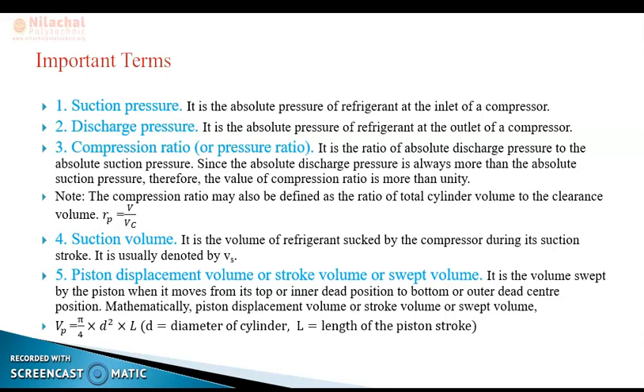The next term is compression ratio, also called pressure ratio. It is the ratio of absolute discharge pressure to absolute suction pressure. Since absolute discharge pressure is always greater than absolute suction pressure, the compression ratio is always greater than one. In terms of volume, the compression ratio is defined as the ratio of total volume of the cylinder (V) to the clearance volume (Vc), written as Rp = V / Vc.